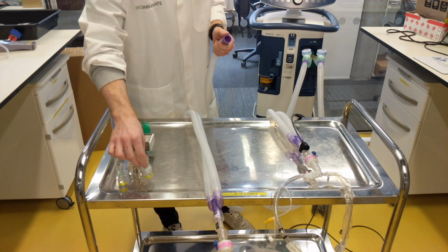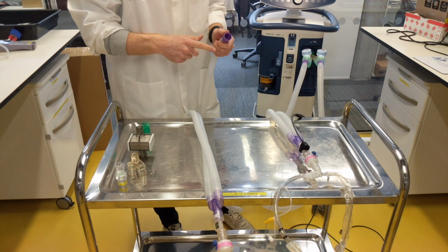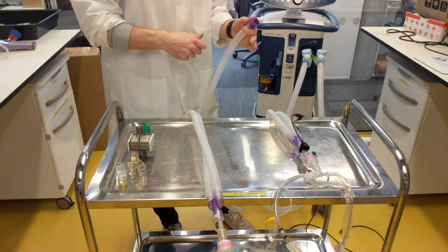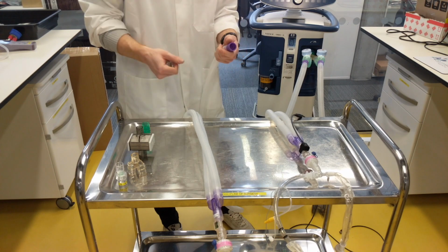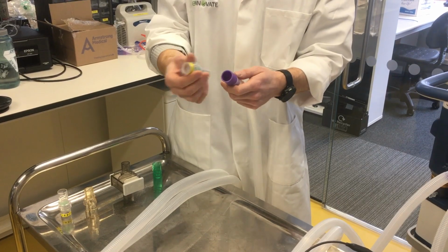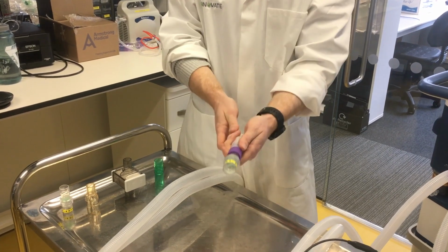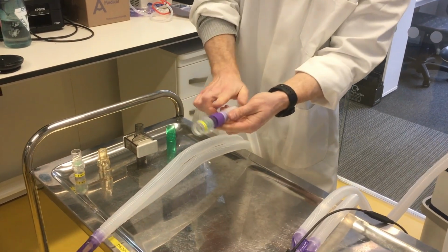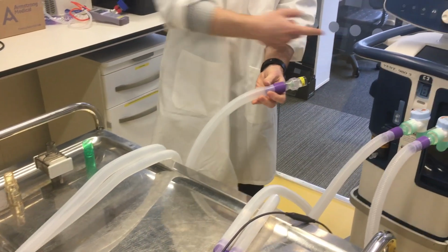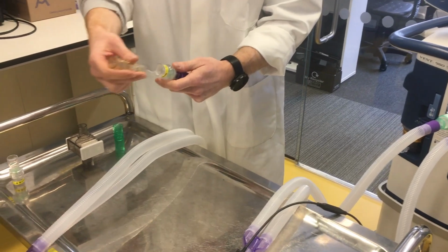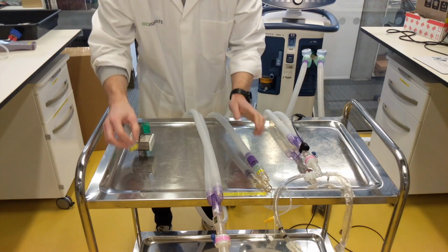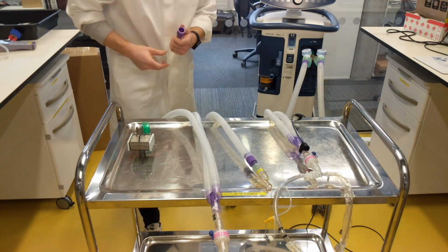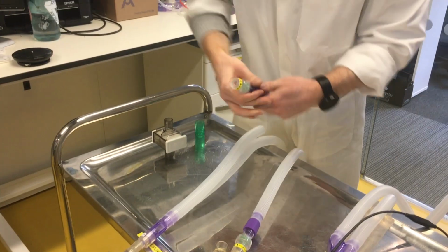A second reason that we'll be doing this step is to prevent any crosstalk between the two patients, so that we can effectively adjust either patient independently without affecting the other. So all we need to do for that is run a one-way valve at the end of the expiratory limb, obviously flowing back towards the ventilator. That then will be attached into a standard Y connector. And I'll just assemble the second patient's one-way valve here as well.